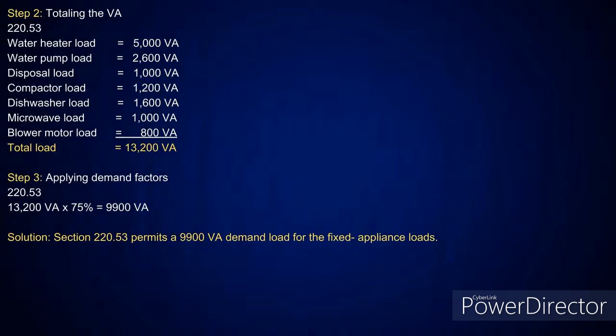Okay? So everything else that's left here, and if you have 3 or less, then you're going to take it at 100%. But I have 4 or more, so I'm going to take it at 75% per 220.53. So I'll take the 13,200 VA at 75%, and then there's my demand load for the fixed appliance load of 9,900 VA. Okay? Nice.